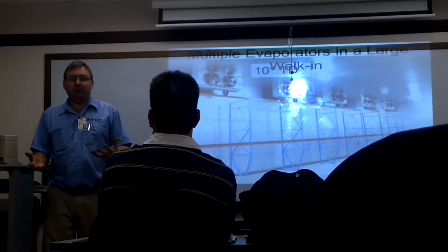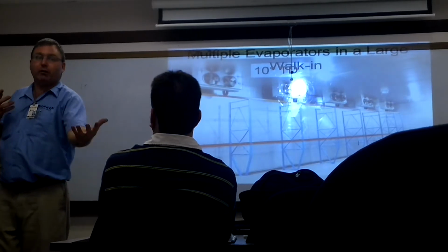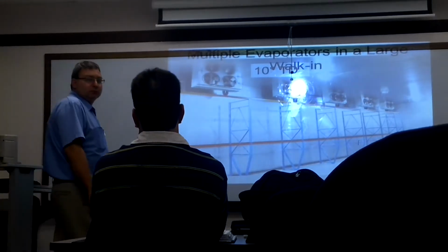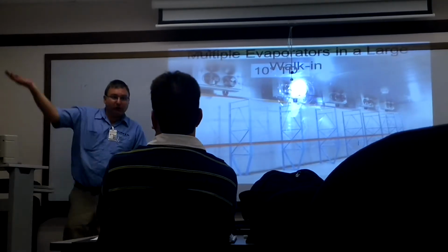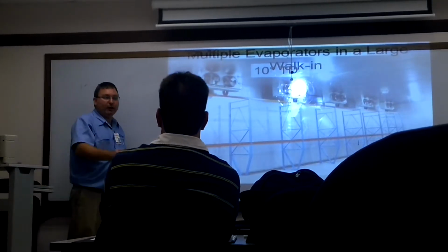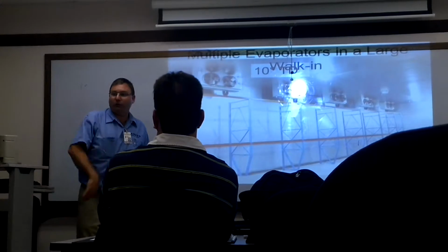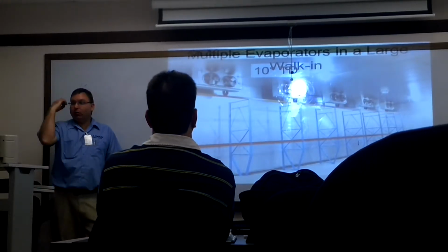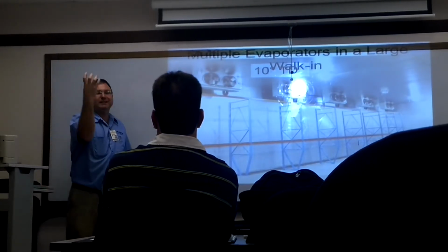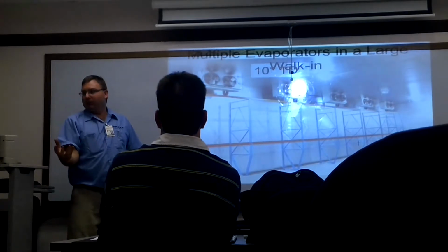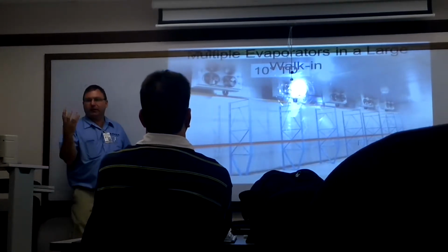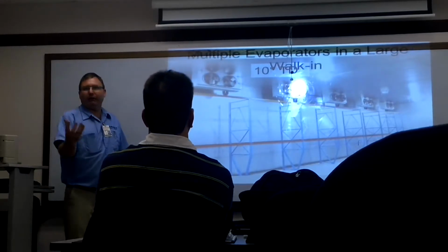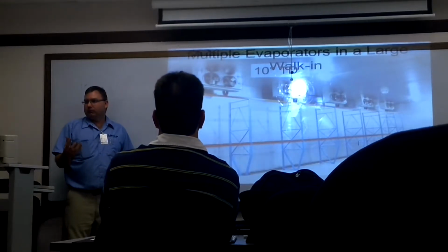So if you've got an expansion valve that's got a piece of dirt in it, are you going to be running low TD or high TD? Brain hurts. Because your suction pressure is going to be lower because you're not feeding the other evaporator coil. So you're going to be running low TD. So that can clue you in on a problem before the customer even sees that you have a problem. And that's what customers love. Customers love the stuff fixed before they have a problem.